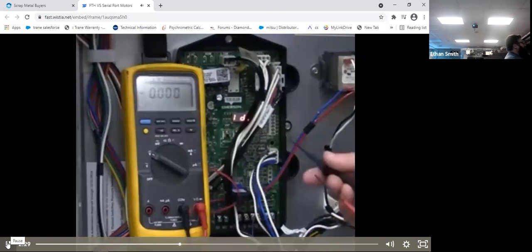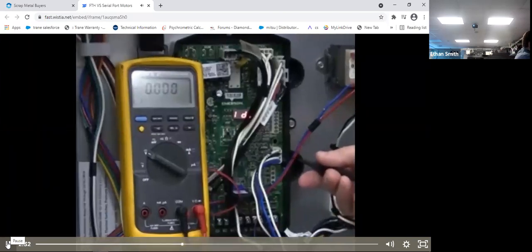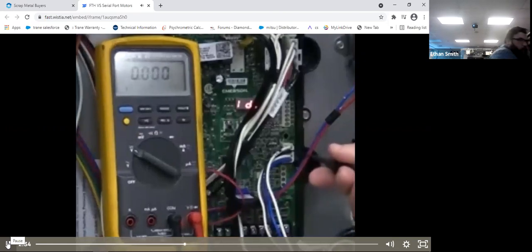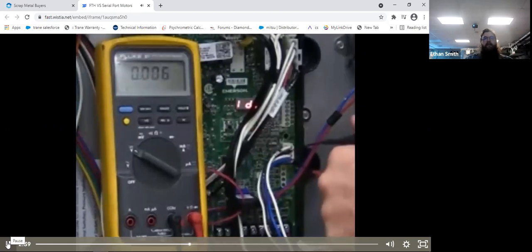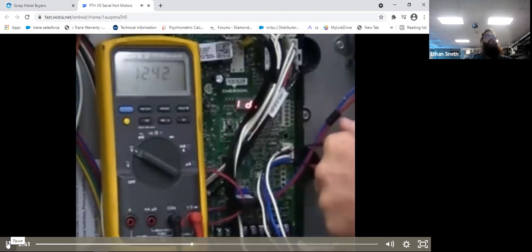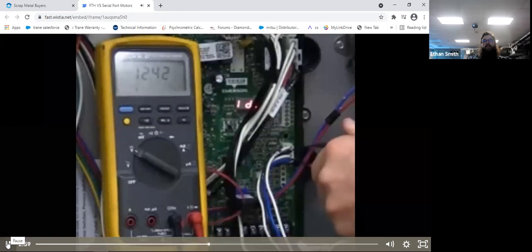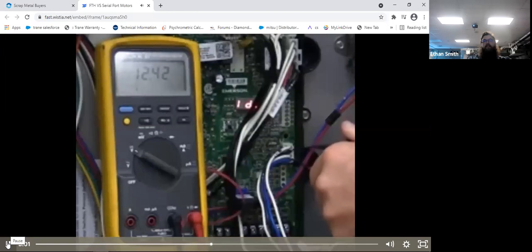If the motor did run, I'm going to start checking voltages from my control board. The black wire is going to be my ground on this test furnace, so I always want to reference my ground for all test points. And then the bottom connector here is going to be my 12 volt charge source. So from my meter, I see I have approximately 12.4 volts DC. Now this DC reading is going to vary whether it's a furnace or an air handler because we run a different power supply within the control board. So look for a source voltage someplace between 12 and 14 volts DC, all depending on the unit. And if I see that, I know that I have source voltage that's going to be able to push the communications to my motor.